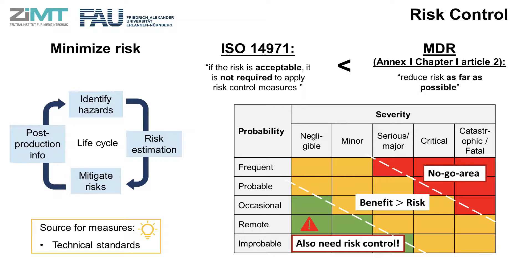The risks have been identified; the next step is to reduce them one by one. Risk control is the step about determining and implementing measures for reducing the risks. Technical standards can usually provide a good source for risk control measures. Although ISO 14971 states that if the risk is acceptable it is not required to apply risk control measures, the MDR requires the manufacturer to reduce risk as far as possible, in Annex 1, Chapter 1, Article 2. As a manufacturer on the market in the EU needs to meet the requirements of the MDR, risk control measures shall be applied to all risks, regardless of their initial acceptability.